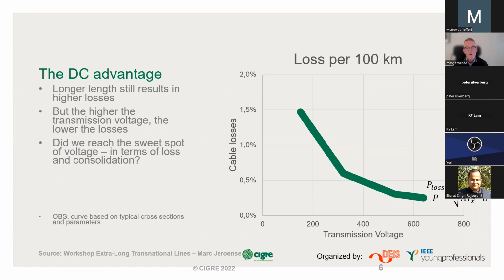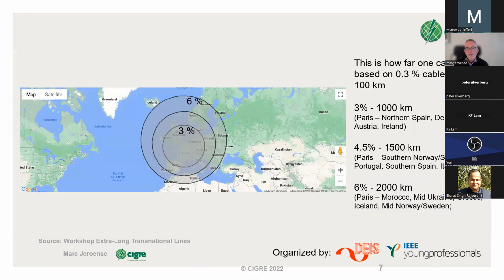At the moment, what I call the sweet spot is this magical number of 525 kV, which everybody talks about. Again, if we want to reduce the cable losses by a factor of 2, we'd have to go to double that, 1050 kV, which is far off what we can do today. So, provenly, looking at all the commercial projects ongoing, we are living with 525 kV for the next couple of years, which is good enough, I would say. The loss we're talking about at this voltage is about 0.3% cable loss per 100 kilometers.